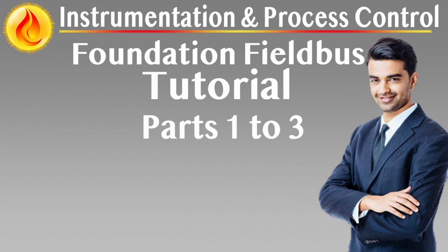savings for complex installations. The technology operates based on a distributed control model. This means control logic can be executed directly within field devices themselves rather than being centralized at the host system. Function blocks reside within intelligent field devices, allowing loop control functions, e.g. PID, analog input, signal select, to be executed locally. This distributed intelligence greatly enhances system response time, reliability, and scalability.